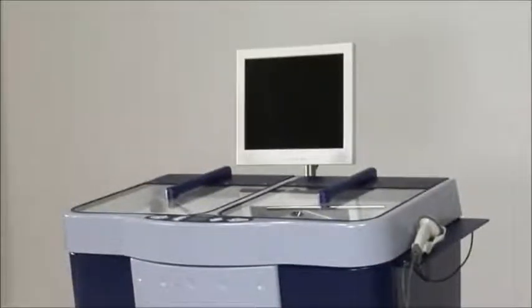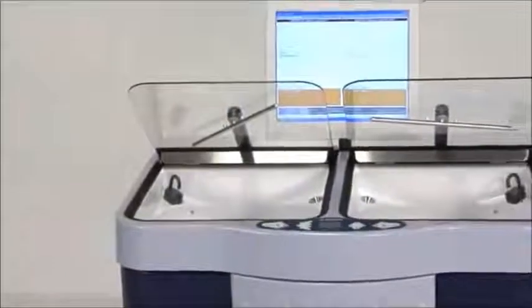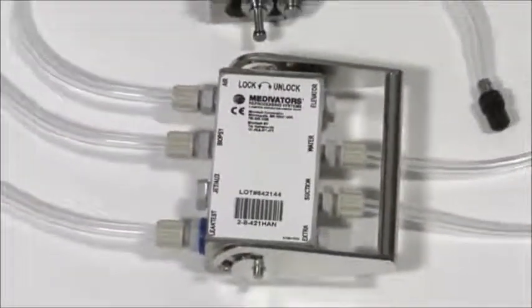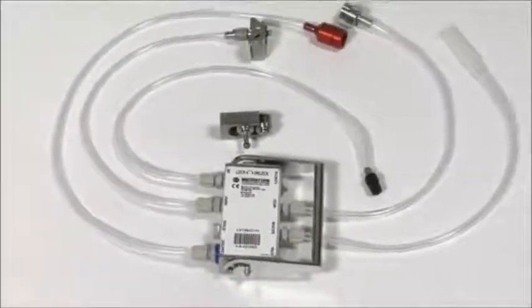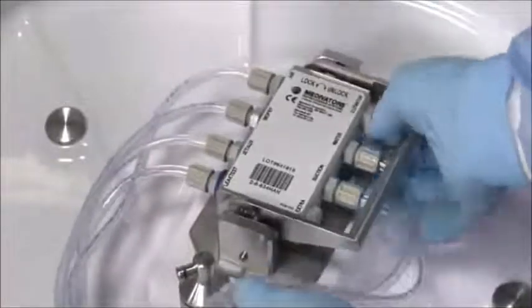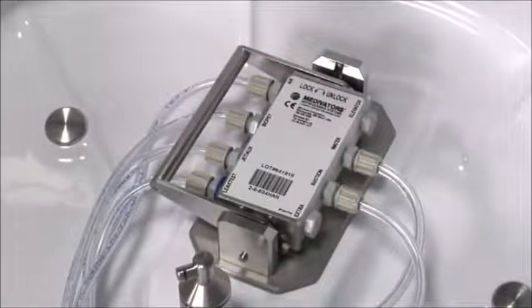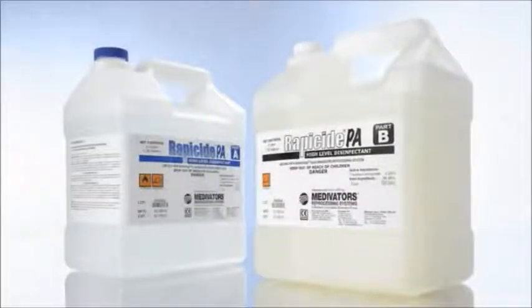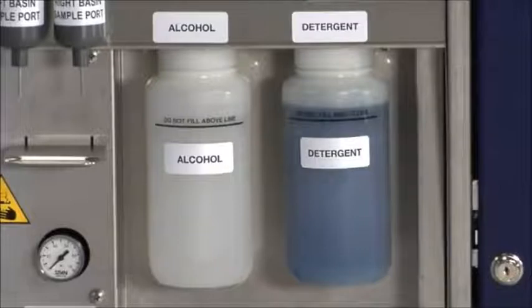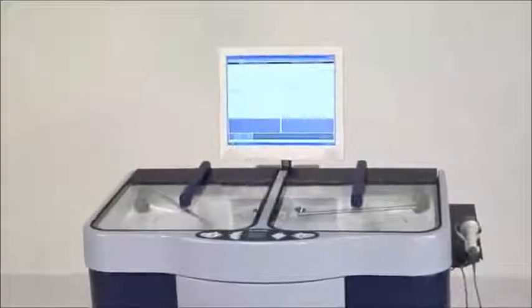The Medivators Advantage Plus system was designed for ease of use and maintenance in the disinfection of endoscopes. Features include asynchronous operation of dual reprocessing basins with transparent glass lids, hookup blocks that are dedicated to a family of endoscopes to ensure correct connectivity, and flow rates that meet manufacturer's specifications, individual channel connectivity and channel blockage monitoring with continuous leakage detection, single-use germicide that provides fresh, high-level disinfectant solution for each endoscope, easy-to-fill detergent and alcohol reservoirs, automated alcohol purge to facilitate channel drying and prevent bacterial colonization, a dedicated personal computer for system operation of reprocessing cycles, cycle recording and reporting, easy backups, networking availability, and remote diagnostics.